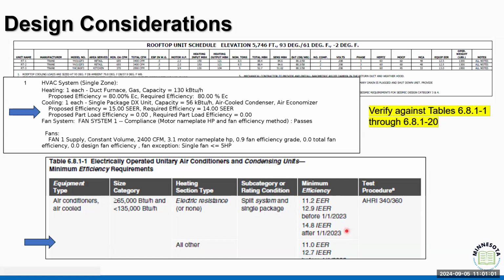That we're expecting a 14.8, because this is going to be a single package system. We're looking for that 14.8 because it's after 2023, and they listed it as a 14.0 - but again, 15 still complies, it meets or exceeds that requirement. So this is where we start to really get into - is this equipment the appropriate size?